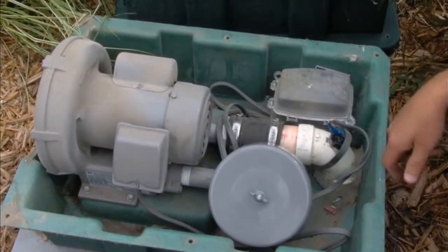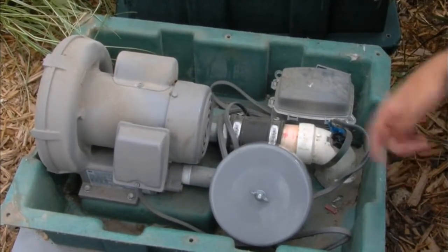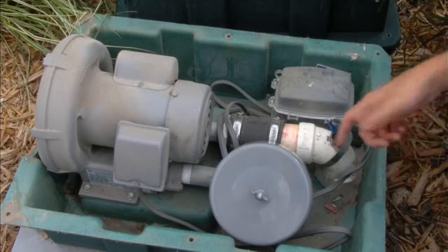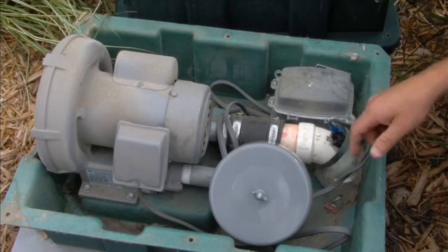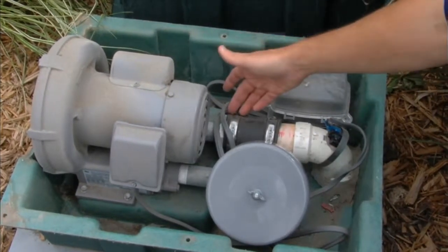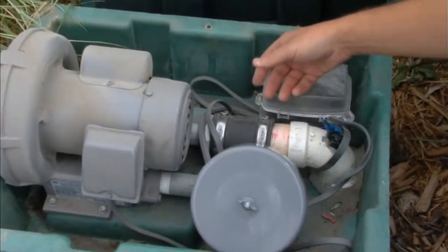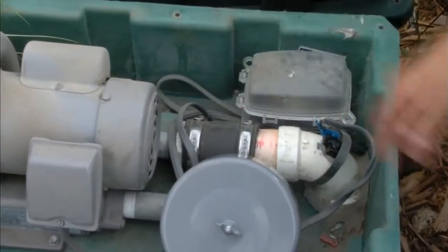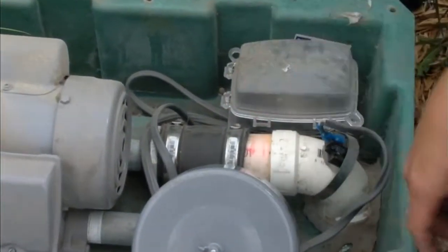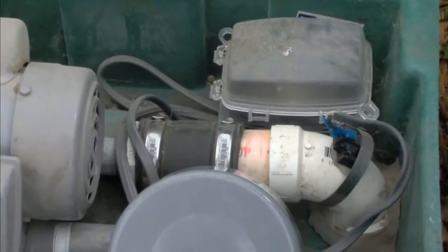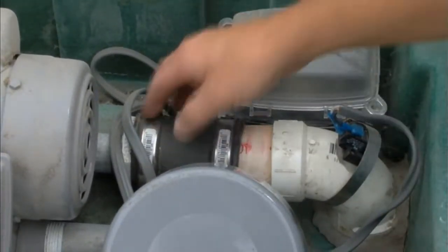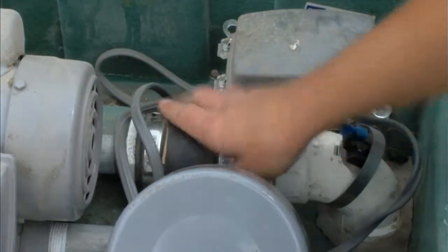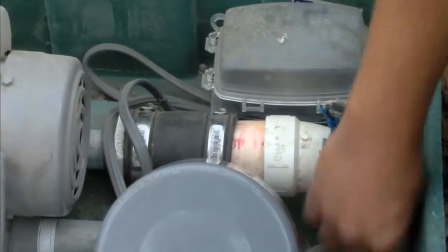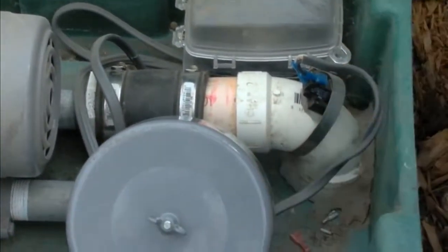While you have the cover off the blower housing, it's a good idea to check your other connections, electrical connections, air connections associated with the blower. First, we're going to look at the Fernco coupling coming off the outlet of the blower. The Fernco coupling is a great device to use just because it makes switching out the blower very easy when that time comes. But just put your hand around the different connections, see if you feel any air coming out. Also, of course, your PVC connections, see if you feel anything there.